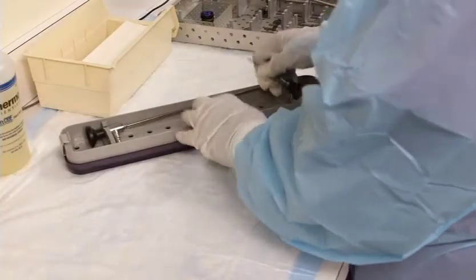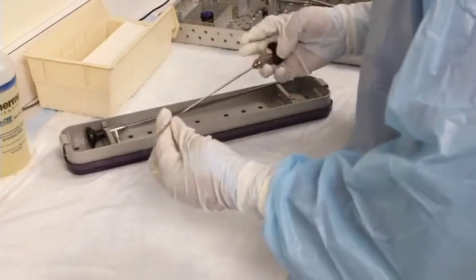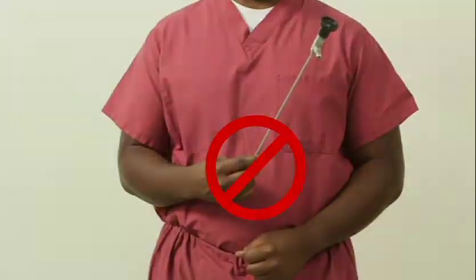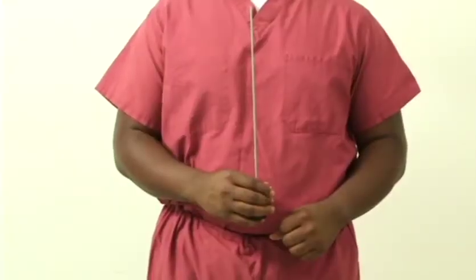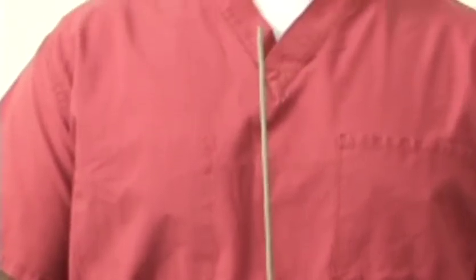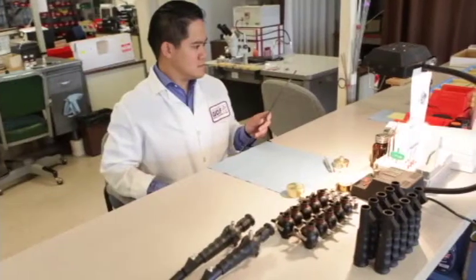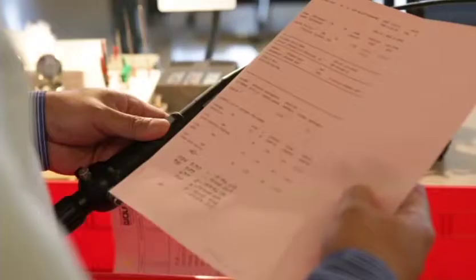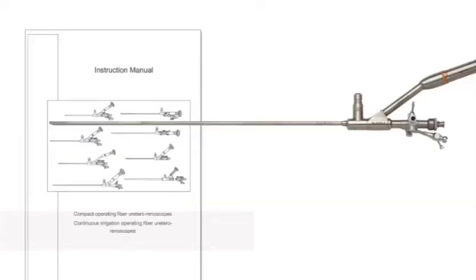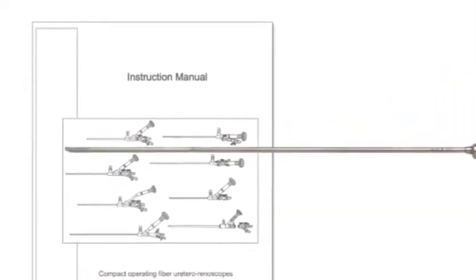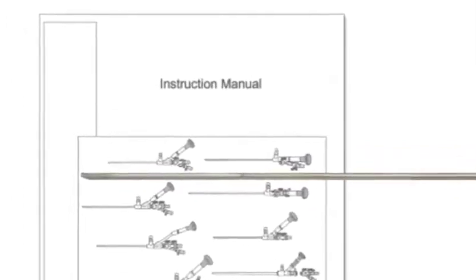Proper handling techniques can prevent damage to the optics and light fibers of the scope. Handle the scope by holding the eyepiece in the palm of the hand and pointing the tip of the scope upwards. This handling technique can prevent bending the scope shaft and damaging the objective lens and eyepiece during transport. Scope damages can negatively impact patient care and often result in costly repairs or replacements. Richard Wolf is dedicated to giving you the information that you need to have the confidence to clean the endoscope so that your patient is well cared for in a safe manner. Please refer to the Richard Wolf Instructions for Use Manual for the unique care and handling considerations for each type of rigid endoscope.